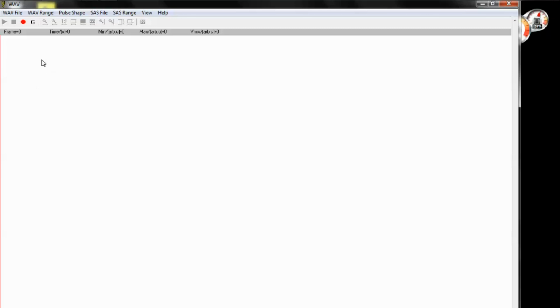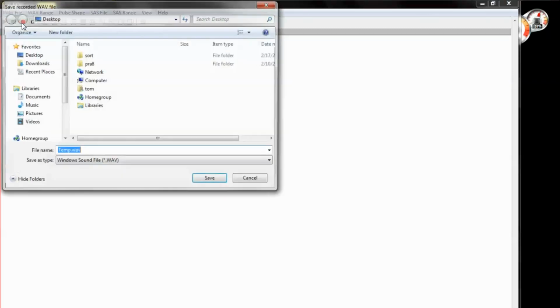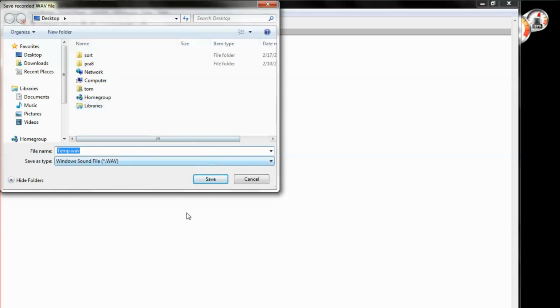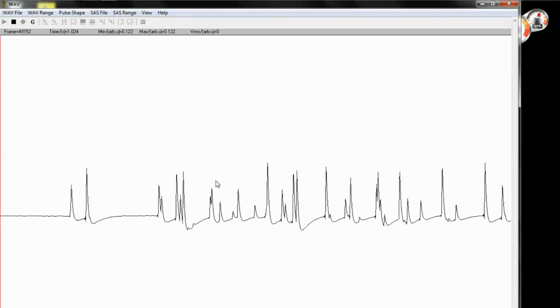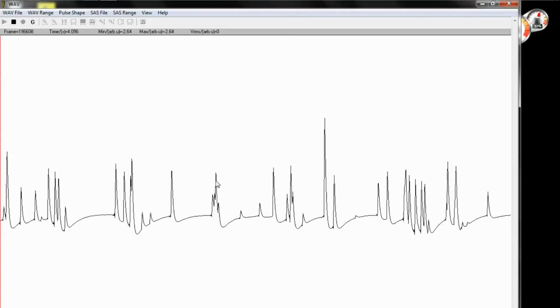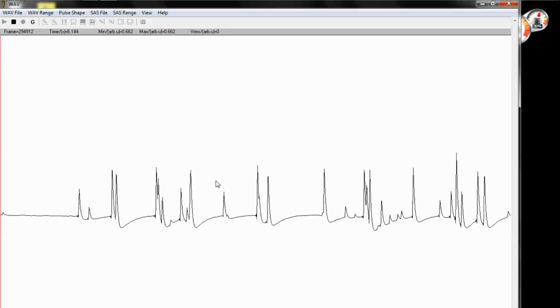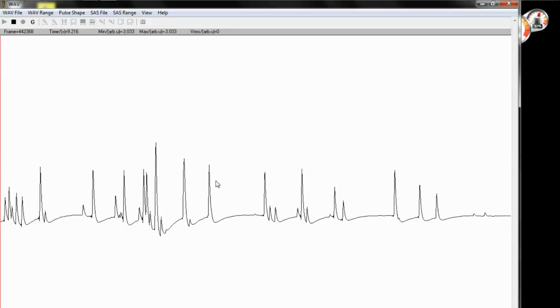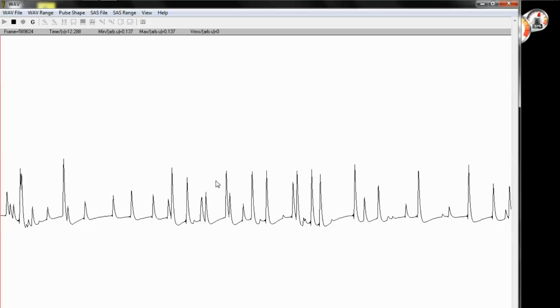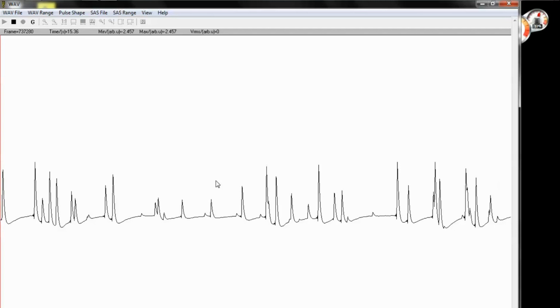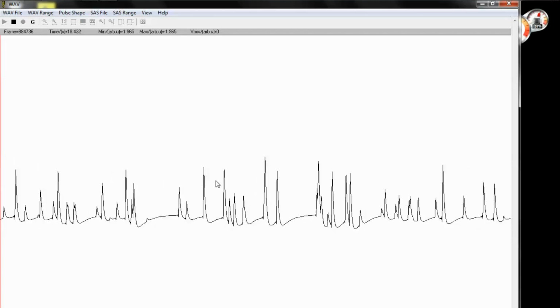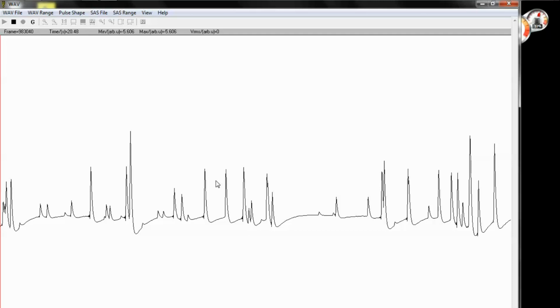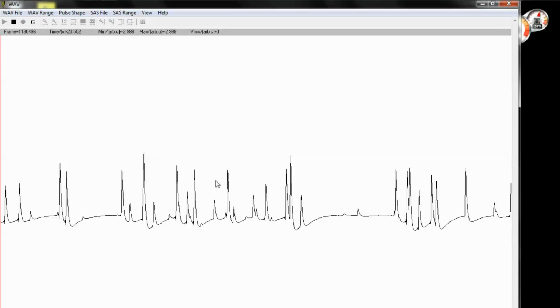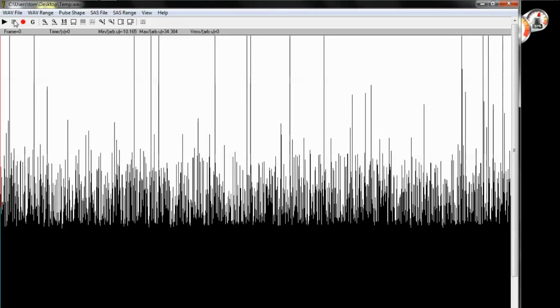All right, so I have the little dial set to 850 volts, and I'm going to click this button right here to record, and it asks where I want to save it. I'm just going to save it to the desktop. It doesn't really matter what file I save this to because I'm not going to use this file. And here's my sound. See it going through? That's actually coming from the cesium-137 source. I'm going to sample a couple of seconds. What I'm trying to do is figure out if my sound is too weak or too strong or what's wrong with it, if it's right. I guess the longer you do this, probably the better. What I'm trying to look for is the sound to be in the right spot. So let's stop this, and I'll show you what I mean by that.